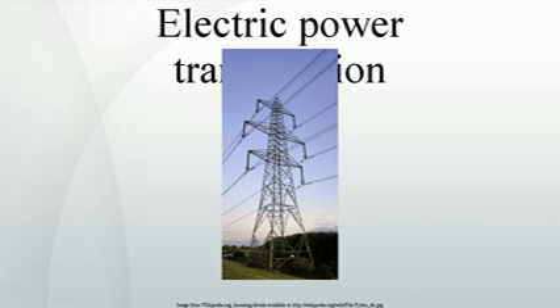Because of this current limitation, multiple parallel cables, called bundle conductors, are used when higher capacity is needed. Bundle conductors are also used at high voltages to reduce energy loss caused by corona discharge. Today, transmission level voltages are usually considered to be 110 kV and above. Lower voltages such as 66 kV and 33 kV are usually considered subtransmission voltages but are occasionally used on long lines with light loads. Voltages less than 33 kV are usually used for distribution.